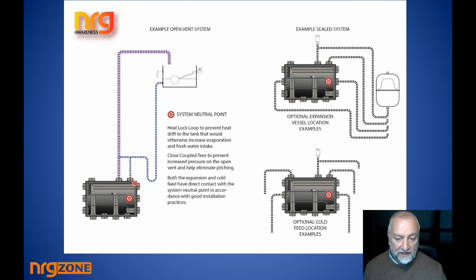The cold feed is open to atmosphere, and therefore if the water has any kind of a, let's say, a negative force, the water will move down in the tank, and if it has a positive force, it will move up in the tank, or vice versa. And the same applies to the expansion. Remember, the water level in the tank is the same water level in the expansion pipe, so in effect they can oscillate up and down to suit whatever's going on in the system. But because, as I said earlier, the two of these connections are about 75 mil apart, it isn't a great issue, because you'll find there's very, very little pressure differential here, and when you do it this way, the water barely budges in the system whatsoever, and that's extremely useful.